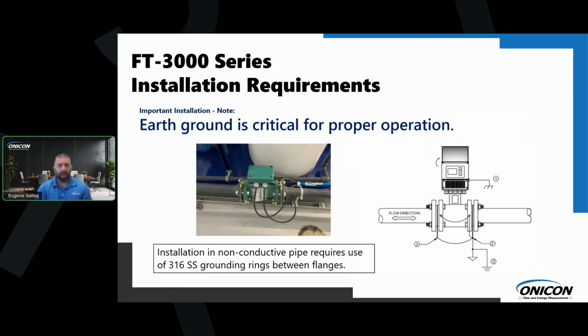So for non-conductive pipe, your PVCs, your HDPE pipes, and any other non-conductive pipe, we do require and always recommend the use of grounding rings or grounding probes. Grounding rings typically are going to be used with the inline mag because they're sandwiched right in between the flanges. What this does is it provides a path to ground for any possible noise or extra electrons, instead of finding a path to ground through our meter, which could cause some possible interference. These meters are picking up small voltages that are induced into the water, so they are sensitive.